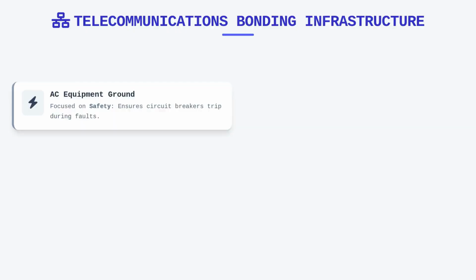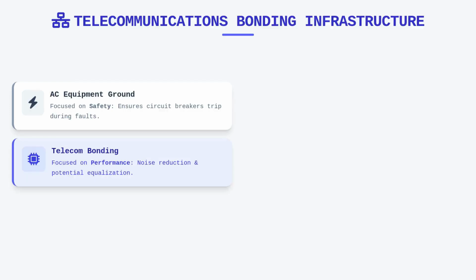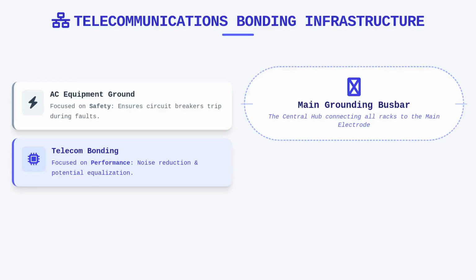The telecommunications bonding infrastructure acts as an extension of the AC system, specifically tailored to the needs of IT hardware. While the AC equipment ground ensures the circuit breaker functions during a fault, the telecom-specific bonding system addresses noise reduction and potential equalization across the distribution backbone. You should view the telecommunications main grounding busbar as the central hub for this specialized system, effectively tying all rack-mounted equipment to the building's main grounding electrode.